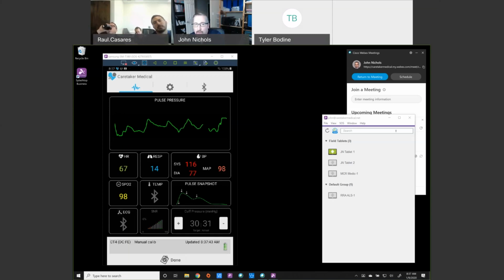If you look in the bottom right corner of the tablet screen, you'll see there's a cuff pressure area, and you'll see plus and minus on either side. You really don't need to adjust the cuff pressure other than if you have a patient say, oh my gosh, this thing's on really tight. So if the cuff is on very tight, you can use the minus to subtract pressure in the finger cuff. If you look right next to the cuff pressure, you'll see SNR, which is the signal quality that we're getting from the cuff. Right now, we've got full bars. If we're not getting a good signal off the cuff, you might see only yellow bars.